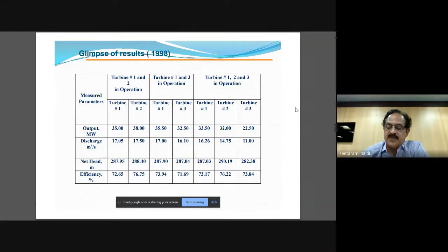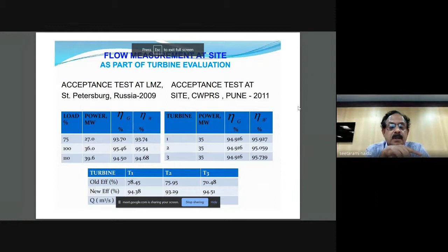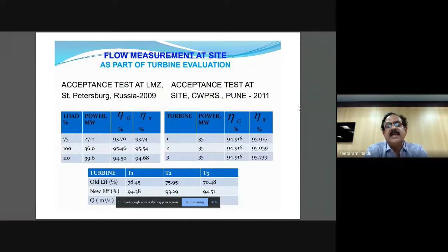The specification was finalized. A new global tender was taken. One supplier fetched the order. It was not BHEL, but some Delhi company, Power Equipment Limited, something like that, with Russian collaboration. The turbine unit was tested at LMZ St. Petersburg, Russia in 2009. The guaranteed efficiency was 93.74 at 75% load, that is 75% of 35 megawatt; at 100% load 95.46; and at 10% overload 94.5. And what they witnessed is similarly higher than the guaranteed.